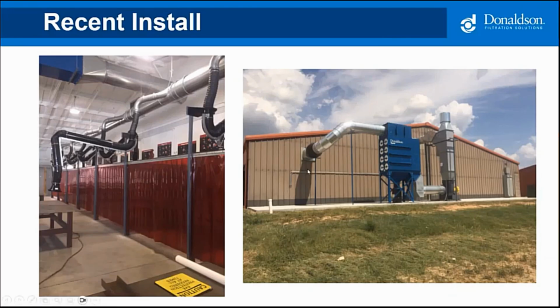Shift your attention now to the outside, and the first thing you see is a spark cooler. This is a spark arrestor. If an ember gets into the system and the ember is lit long enough and gets to the cellulose / nanofiber, FR means it will burn as long as it has a match to it. But if the ember extinguishes itself, it will quit burning.